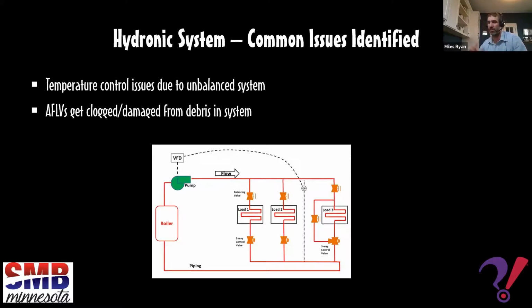However, in recent years, that particular facility has not done any treatment of their water. They don't have any side stream filters. They haven't been doing any chemical treatment of their water. It's gotten quite dirty, and now we're having a bunch of these cartridges get clogged. And now some units are not getting any flow. We also had a couple of examples where we're actually leaking out of those valves. And now we're back in the building, and we're addressing cleaning up that water in the system so we can get back to operating well like it did the 3 years prior to this winter.